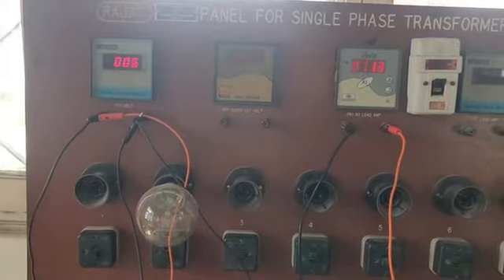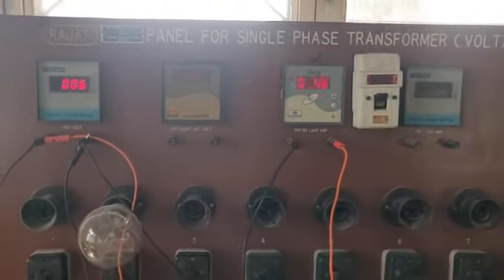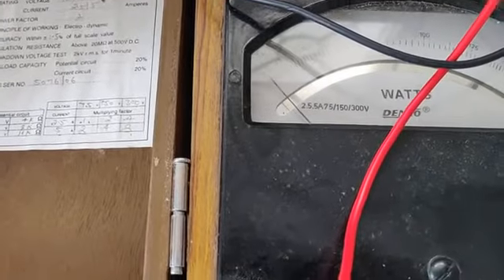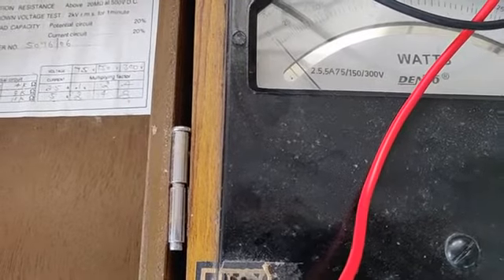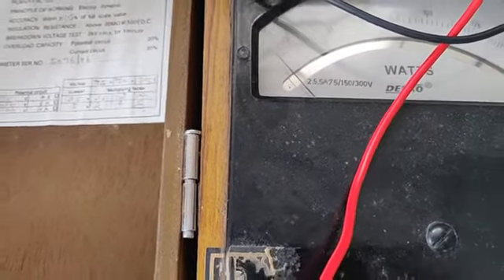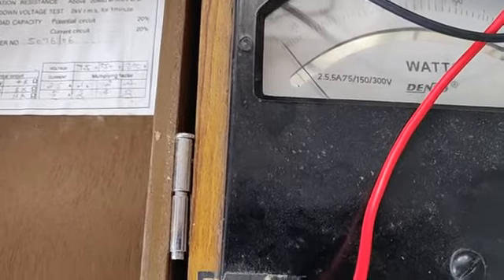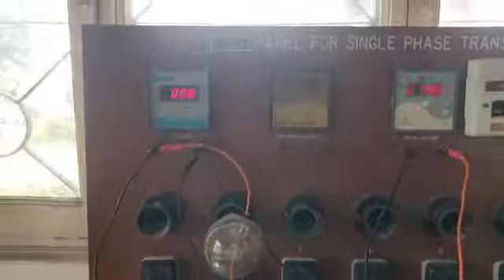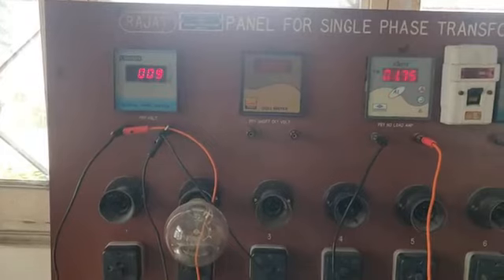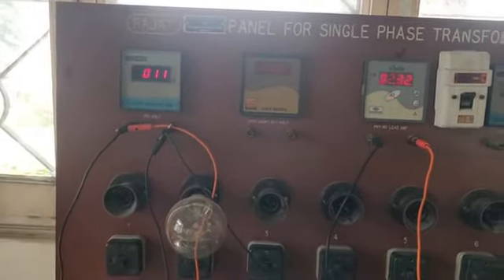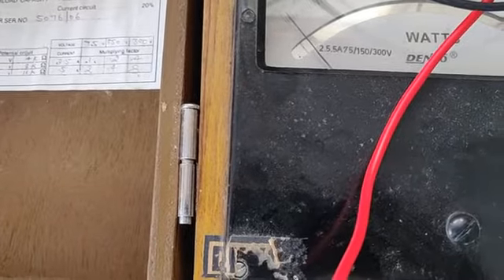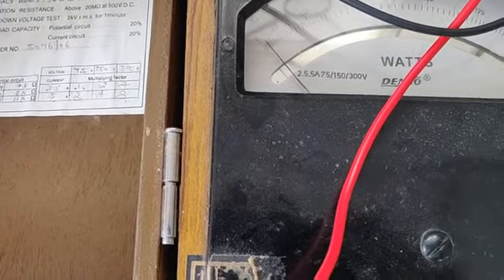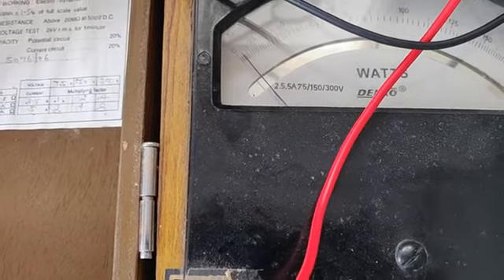Say second reading: voltage is 6 volt, current is 1.46 ampere, and the wattmeter reading is on second division. Here you find the least count. So next and last reading is, if voltage is 11 volt, current is 2.32. In this case, the reading of wattmeter is on fourth division. So first find out the least count, then find out the copper loss in a transformer, and copper loss is given by the wattmeter.